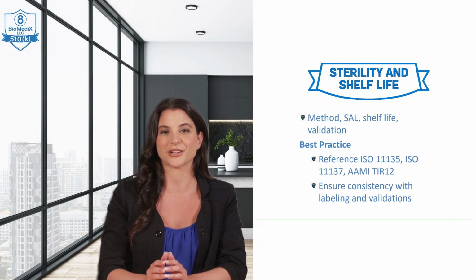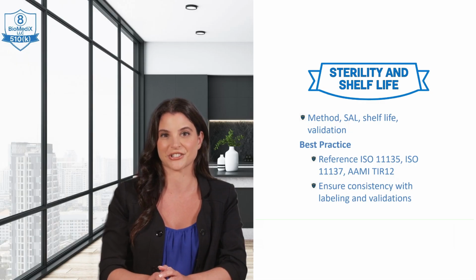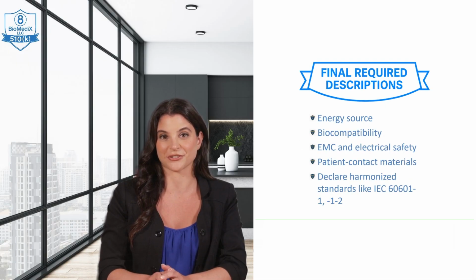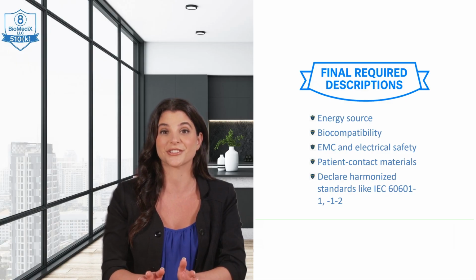For sterilization parameters, if applicable, if the device is supplied sterile, you'll be asked to provide the sterilization method, sterility assurance level, typically 10 to the -6, claimed shelf life, and validation method. If the device is reusable and sterilized by the user, you'll describe the reprocessing instructions and validation methods for those instructions. The best practice is to reference relevant consensus standards such as ISO 11135, ISO 11137, or AAMI TIR12, and provide a summary of your validation studies. Ensure your labeling clearly reflects these parameters.